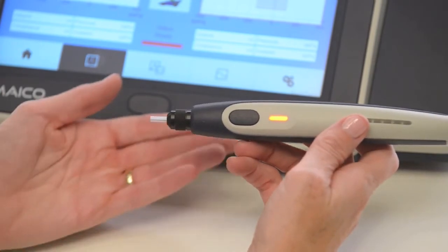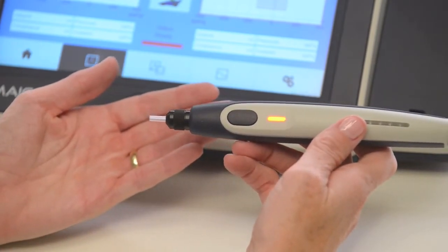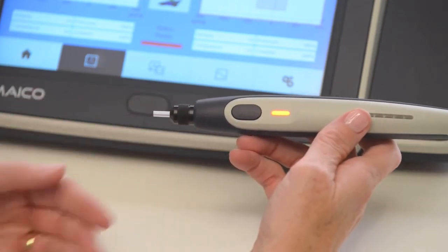If there is an obstruction, clean the probe tip using the tool provided. An occluded probe could result in flat tympanograms and may damage the probe.